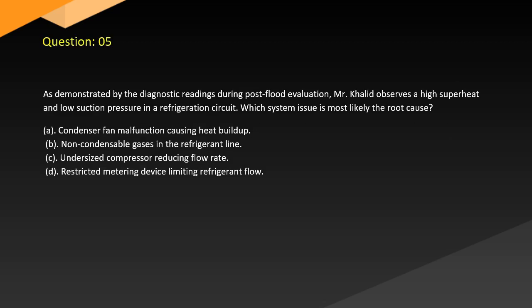Question 5. Demonstrated by the diagnostic readings during post-flood evaluation, a technician observes a high superheat and low suction pressure in a refrigeration circuit. Which system issue is most likely the root cause?